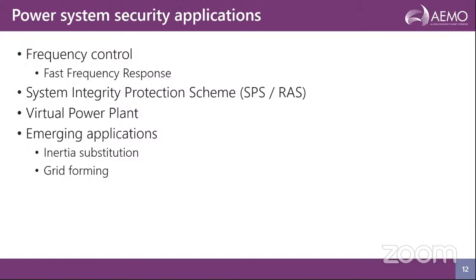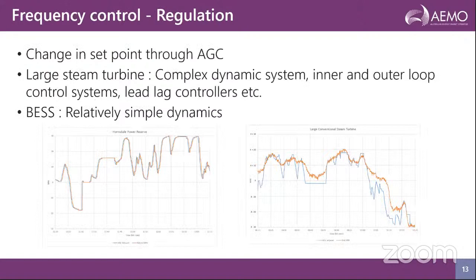So let's look at the first one, the frequency control. I've divided that in two parts, the regulation and the contingency. This slide shows how a battery, particularly in regulation services, that is, correcting the small changes in the frequency through the automatic generation control system, AGC, would respond. The figure on the left is a comparison between the command set by our AGC system and the response from the battery. The figure on the right is the response from a large conventional steam turbine. The duration of this figure is 1 hour in both figures. So it's clear how the battery closely follows the AGC target as compared to a conventional steam turbine.